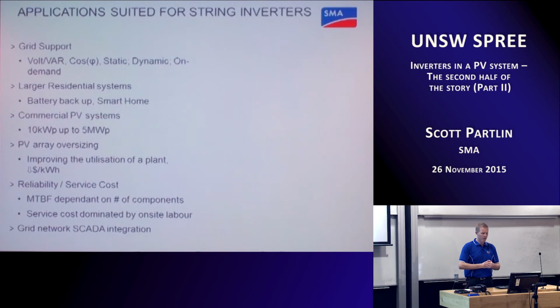And then obviously grid network SCADA integration. So once you get to larger and larger systems, your plant may be required by the grid operators to be integrated into their SCADA network so that they can have some level of direct control. Now at the moment, based on my understanding, that is exclusively string and central inverters, and even within SMA at the moment, our microinverter solution, we're not able to integrate that into a SCADA system, mostly because SCADA systems are only required for large systems, and our microinverter product is pitched at that sweet spot around the 3 to 4 kilowatts. But we'll talk about SCADA a bit in the next one.